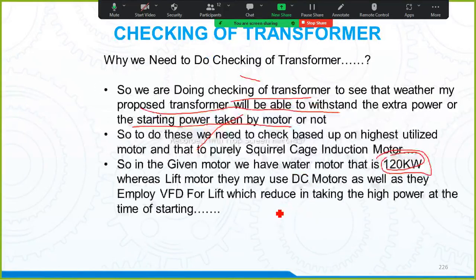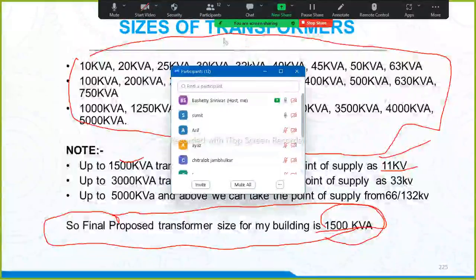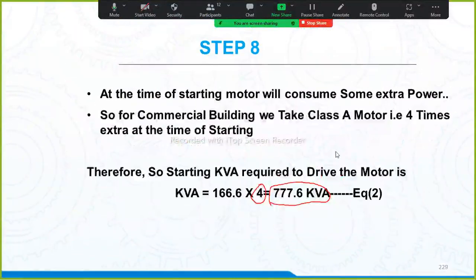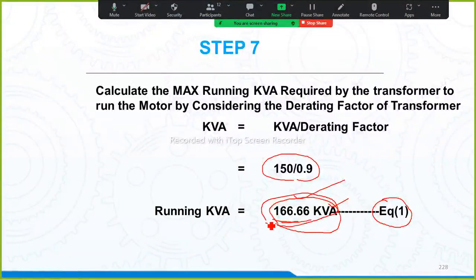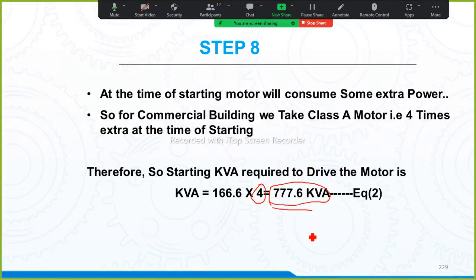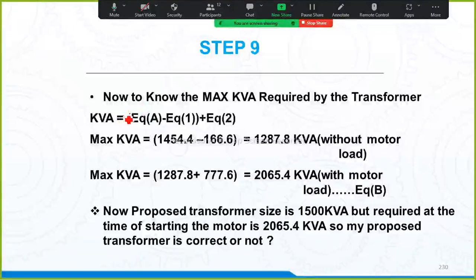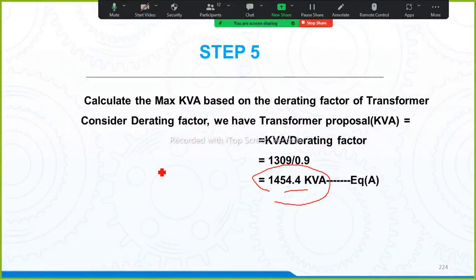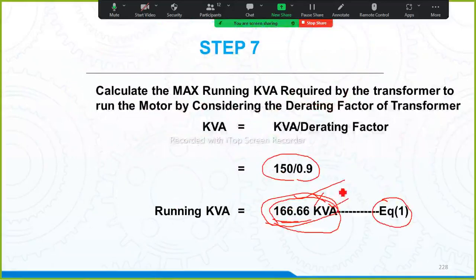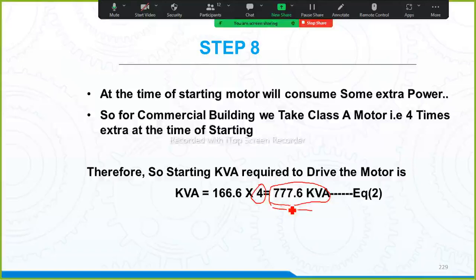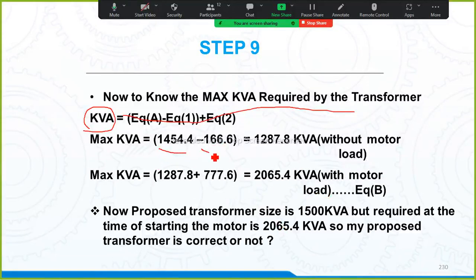When we did the calculations in the first 5 steps, which kVA did we take? We took the running kVA, 166.66 kVA. Now I need to remove this running kVA from the main kVA and add the starting kVA, which is 777.6 kVA. To know the maximum kVA required by the transformer, we take equation A, where we got 1454.4 kVA as the total. Now from this 1454.4 we remove the running kVA and add the starting kVA. So 1454.4 minus 166.6 is equal to 1287.7 kVA without motor load. But at the time of starting, the motor takes high power.